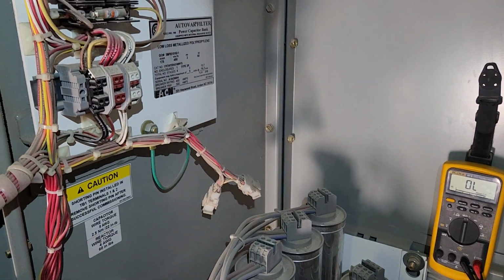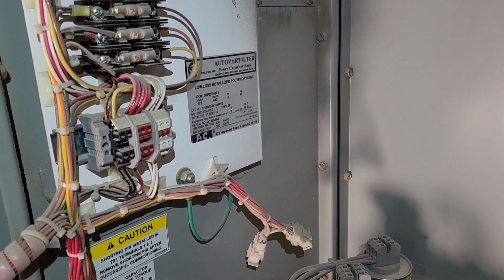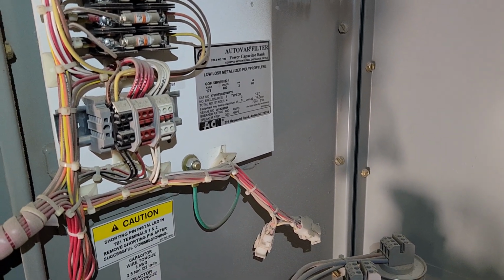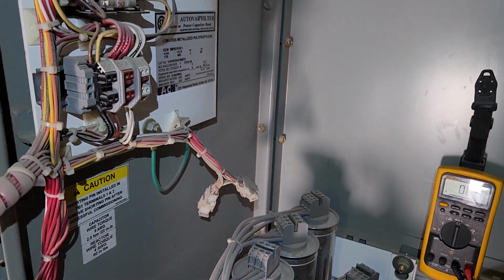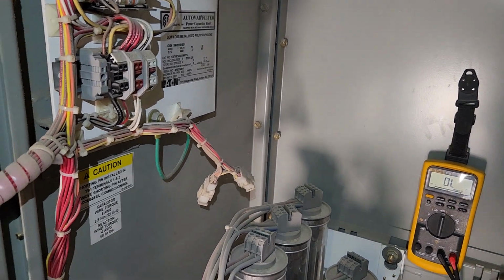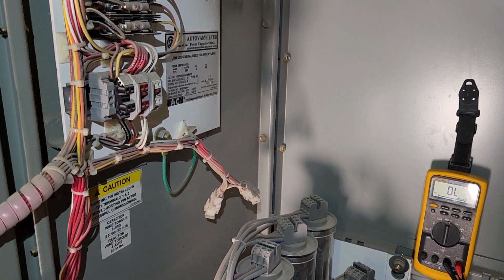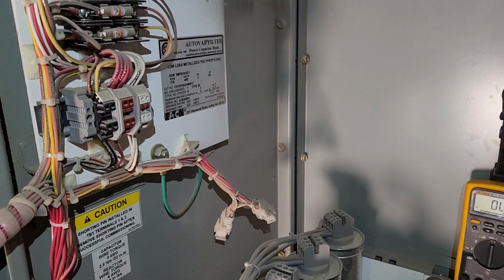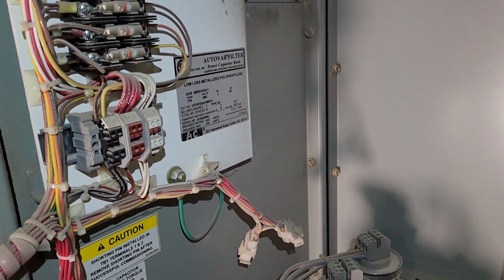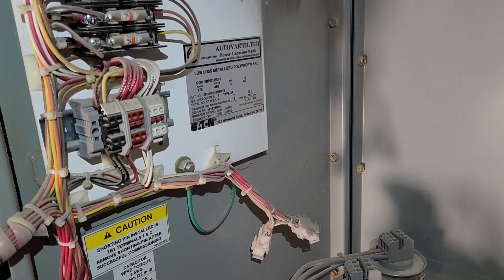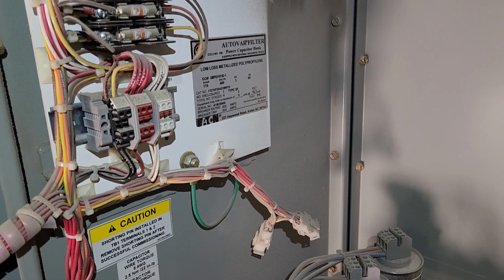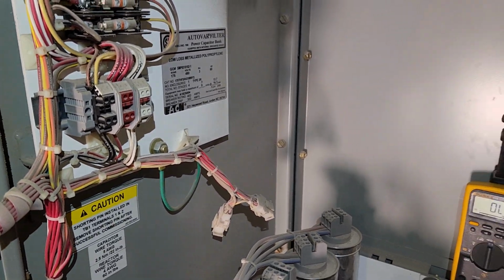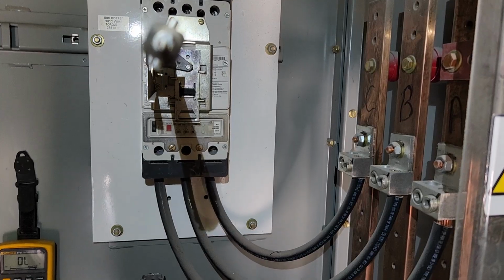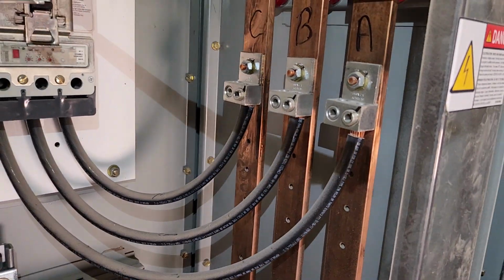And you might be thinking, why would you want to put 200 amps of additional load on your building? Well, it actually does save us quite a bit of money. If we correct our power factor, that 200 amp load for an 8-hour day doesn't make much of a difference. I mean, some of our motors are pulling 250 amps all day long. So this 200 amp load, when it corrects for a power factor, makes our electrical bill cheaper from the power company. So kind of neat.